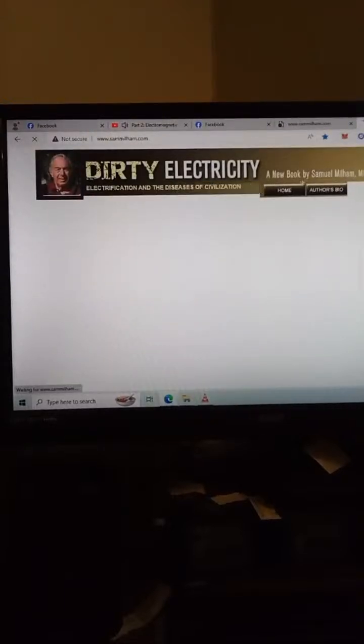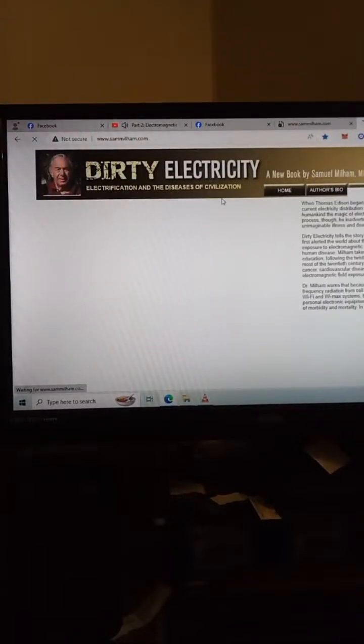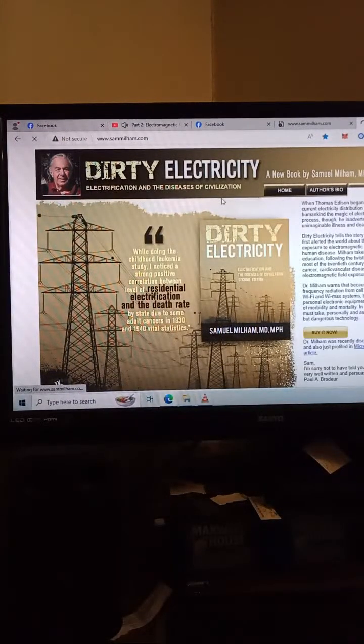When the current gets to the load, the light bulb or whatever the load happens to be, and that current runs back on the neutral wire, whether it's the circuit in the wall or the neutral wire of the lamp cord, then you turn your palm over, and now the thumb is pointing towards you, indicating that the current is coming back towards you on the neutral wire, and the right-hand fingers are curling counterclockwise. So the magnetic field around the hot is going clockwise, the magnetic field around the neutral is going counterclockwise. And when those are brought together, that is how the magnetic field is canceled in the room if those two wires, the hot and neutral conductor, are together and equal.